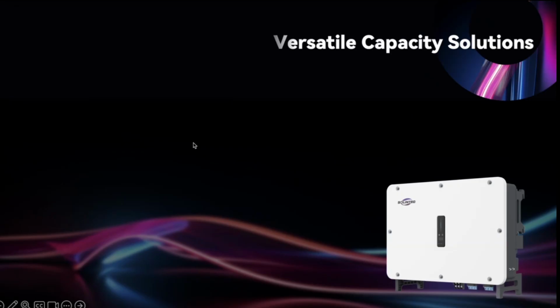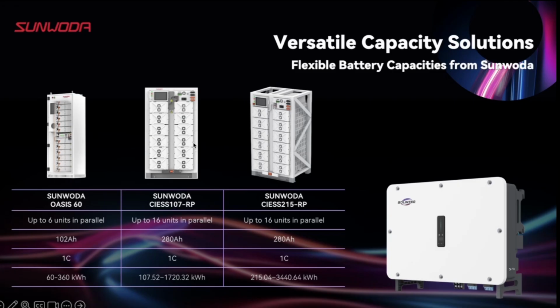And here we can see the battery options that work perfectly with our M2HT hybrid inverter. We have partnered with Sunwoda, one of the top battery manufacturers, to offer a full range of flexible capacity solutions, from the OASIS 60 to the CIESS 107RP and the CIESS 215 RP. Depending on the project size, these batteries can be connected in parallel, up to 6 units for the OASIS 60 and 16 units for the CIESS series, covering total capacity from 60 kilowatt hours to over 3.4 megawatt hours. So it is ideal for both small businesses and large-scale commercial projects.